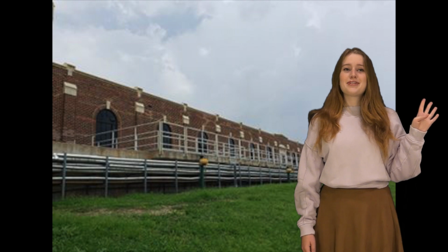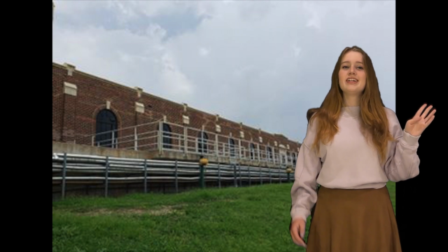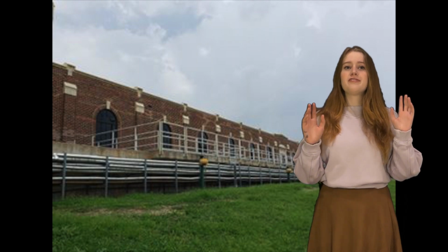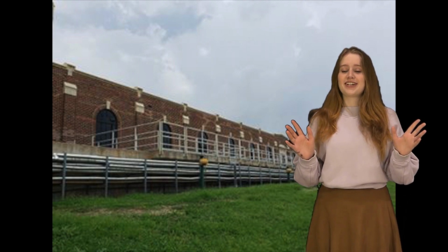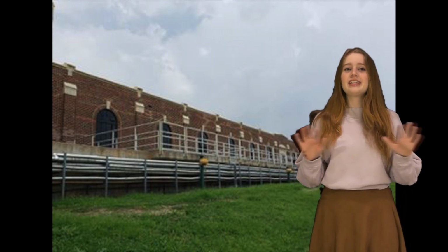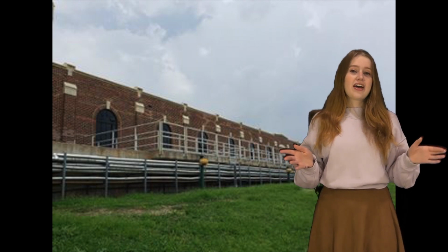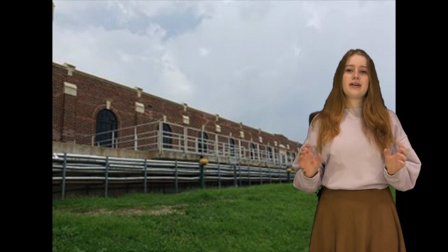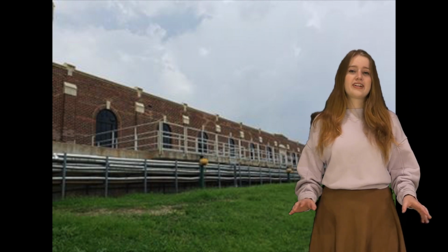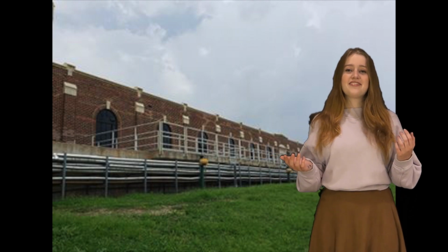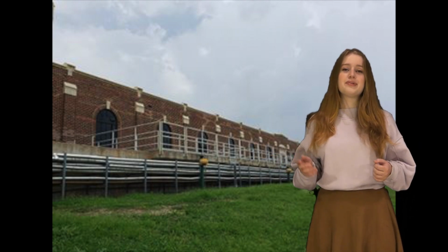The fourth step of this process is sedimentation. Here, the water is moved into a huge pool where it can hold up to 55 million gallons of water. Then they allow the water to sit for a really long time, completely undisturbed. This is so that all those large particles in the water will start drifting to the bottom and fall to the bottom of the pool, where they create a sort of thick layer of sludge. That makes it really easy for them to then suck the sludge out of the pool and leave only the cleaner water behind.